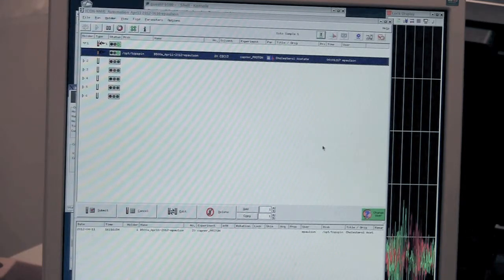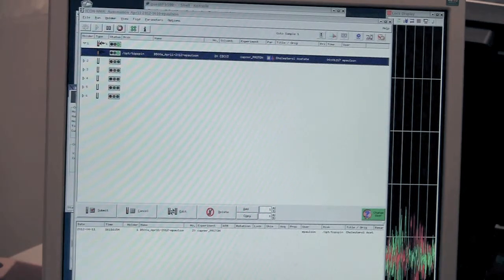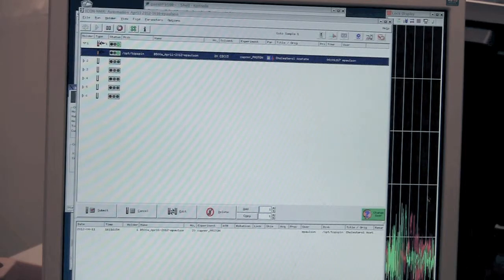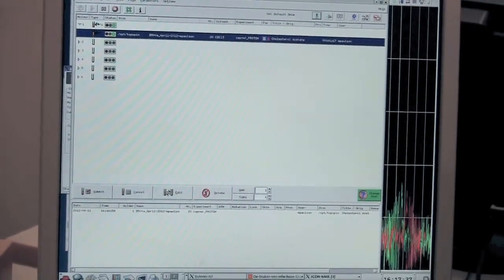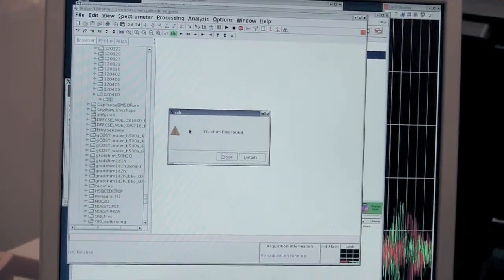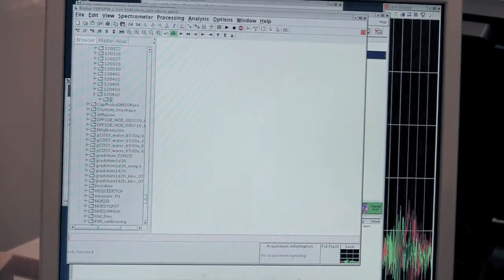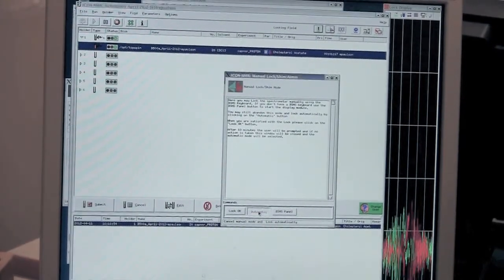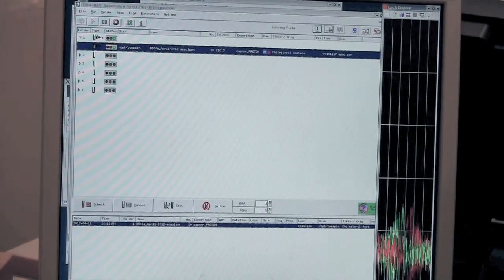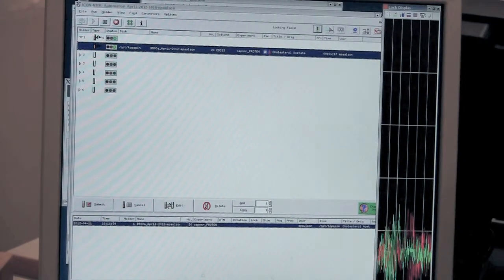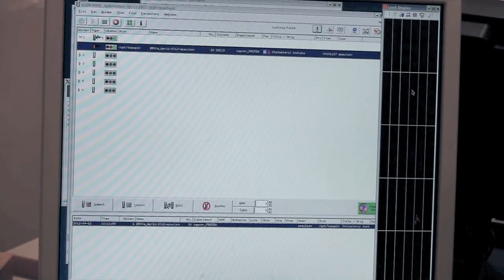So then the next step is to lock. Now the lock signal on the capillary NMR is weaker than it is on the normal because we have so much less solvent. So after you lock, you may see a message; it just means that it didn't load the standard shims. That's okay. So we can do automatic lock, and it should lock in the normal way. But if the signal is noisier than you're used to, don't worry about it too much. Or if it's really noisy, then that can be an indication that there's a problem with your sample. Either there's an air bubble in the way or something is wrong. This amount of noise is reasonable for chloroform on this probe.